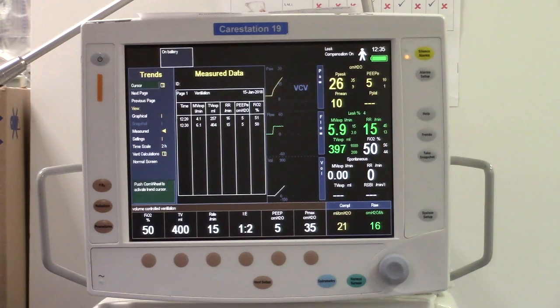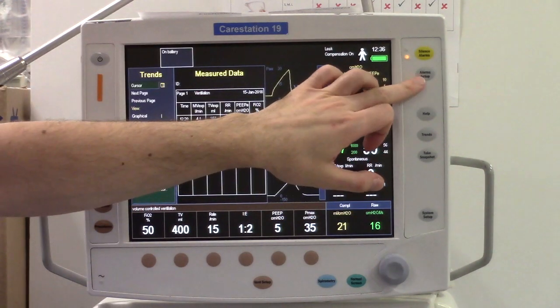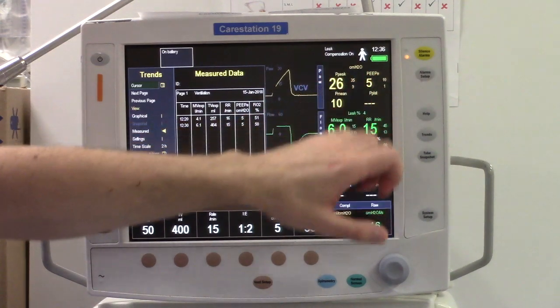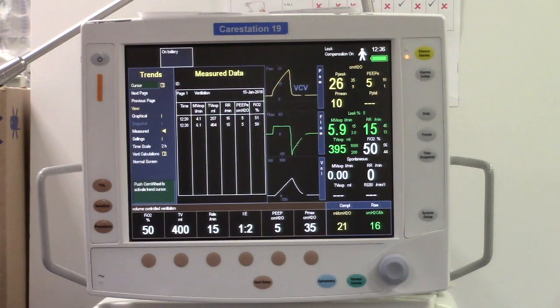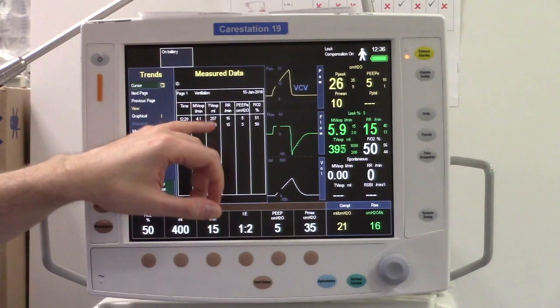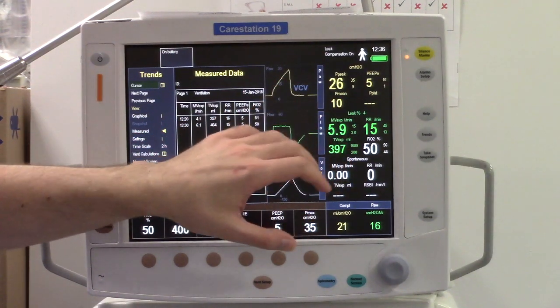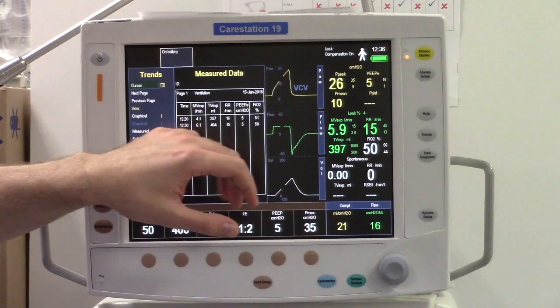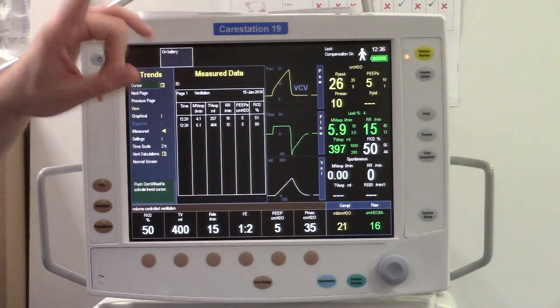Trends is the history of the ventilator, and it stays there unless we reset it, and usually it's reset when we do a pre-use check. And going back to alarm history, it will be reset if the ventilator is switched off. Yeah, compared to trends, which stay there unless we reset them while we do the pre-use check. We have an option there.